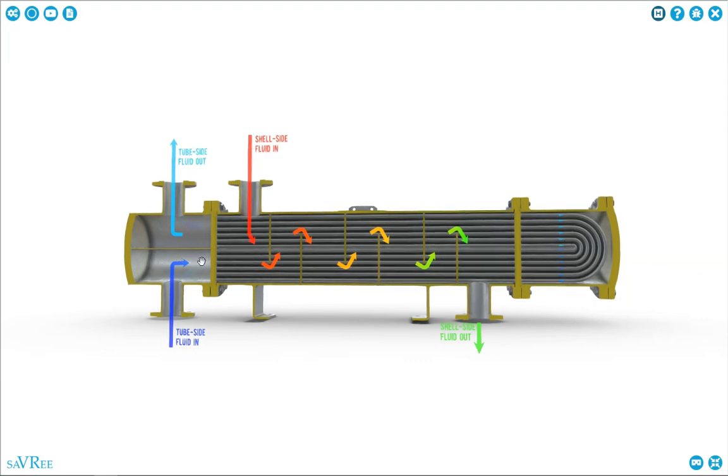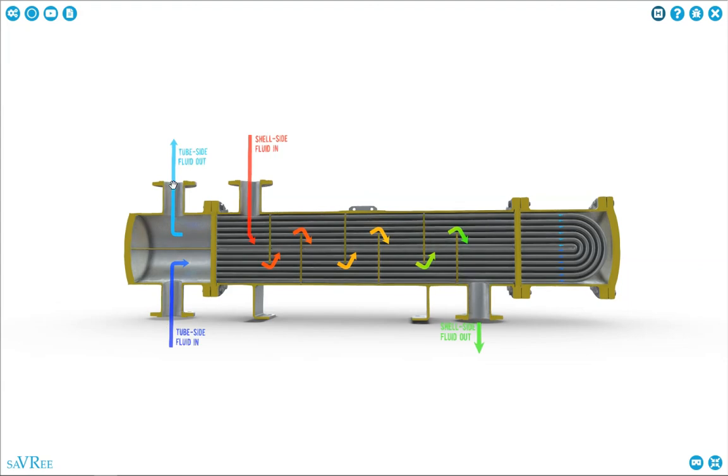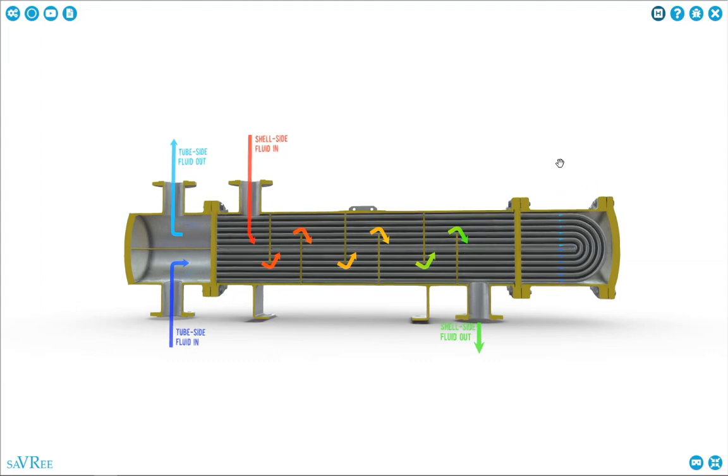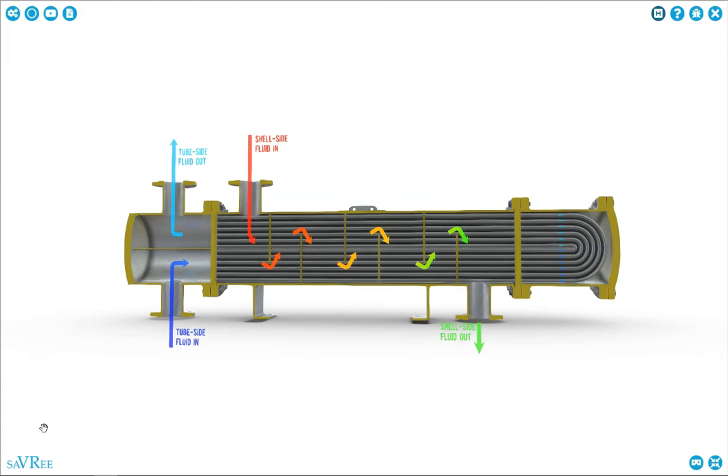This would also be a two-pass design, so it does come back and forth. And typically, a two-pass design, you would have your inlets and outlets on the same side. If it was just a single-pass design, of course, you would start out at one side of that heat exchanger, and it would make its way across to the other side where you would have your outlet if it was a single-pass design. Hope that helped understand a little bit of what you see inside of a few of these heat exchangers.